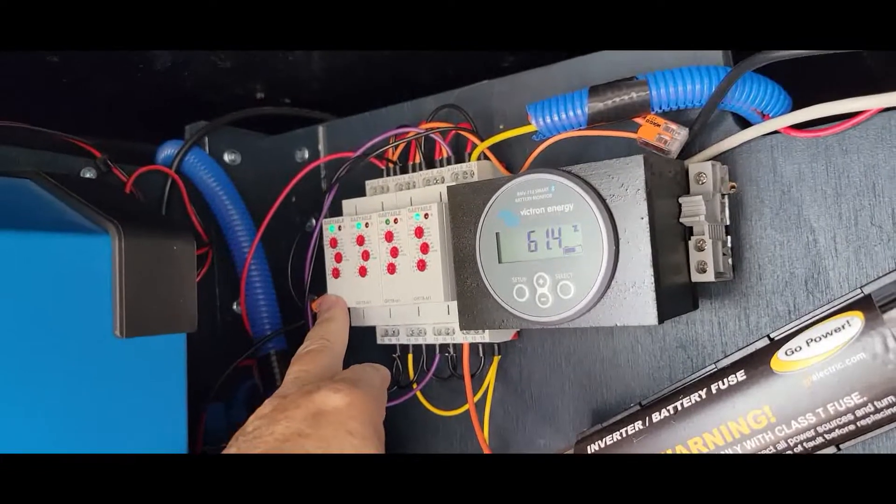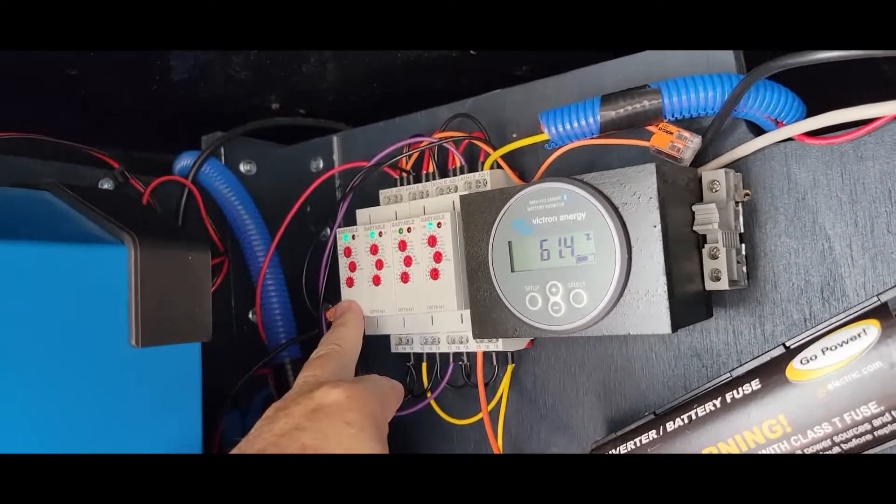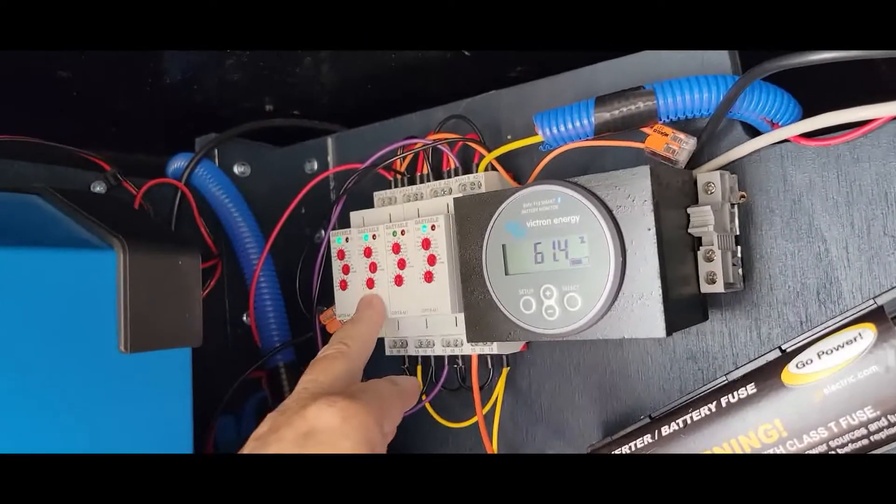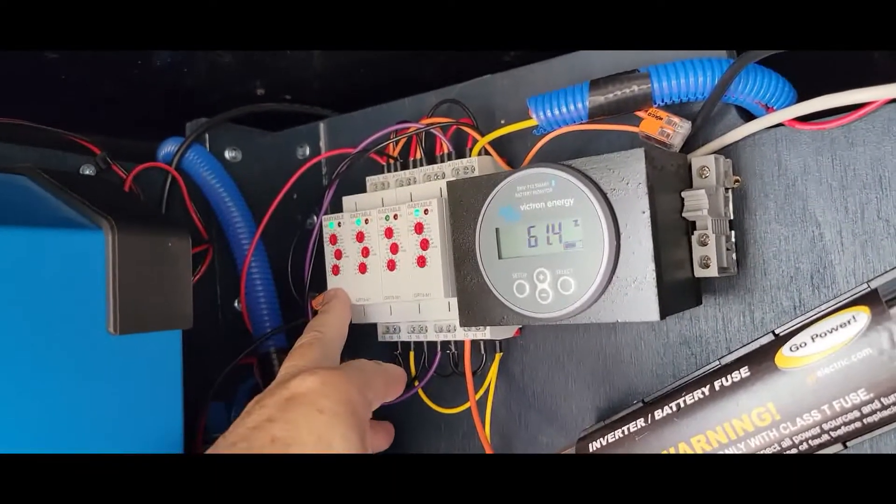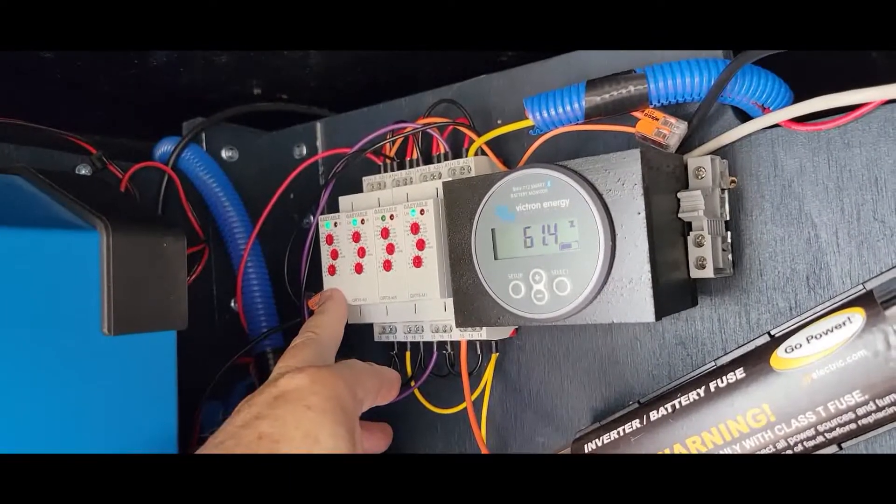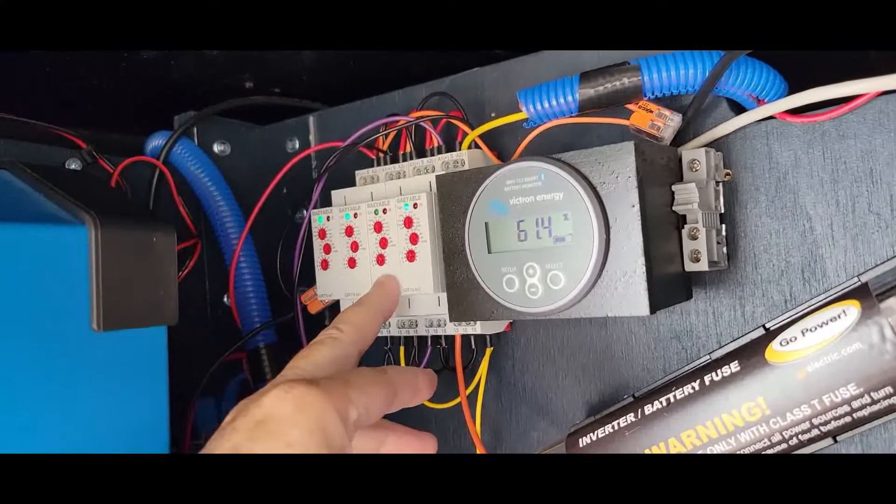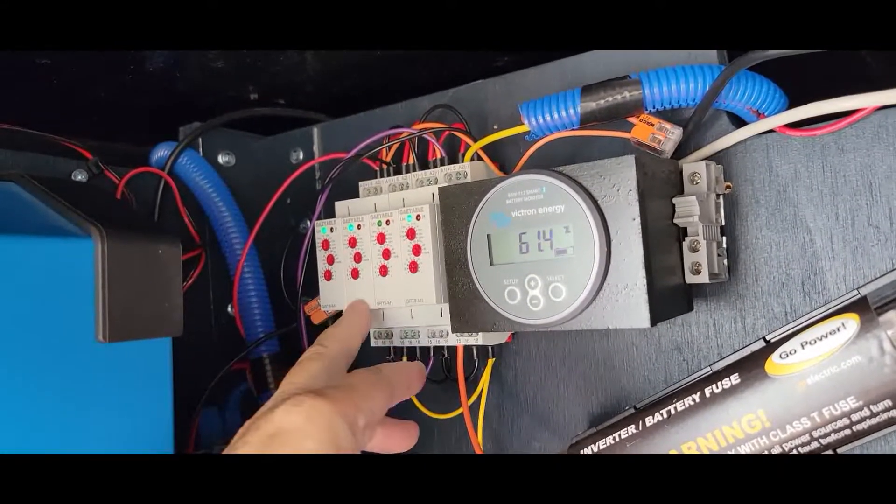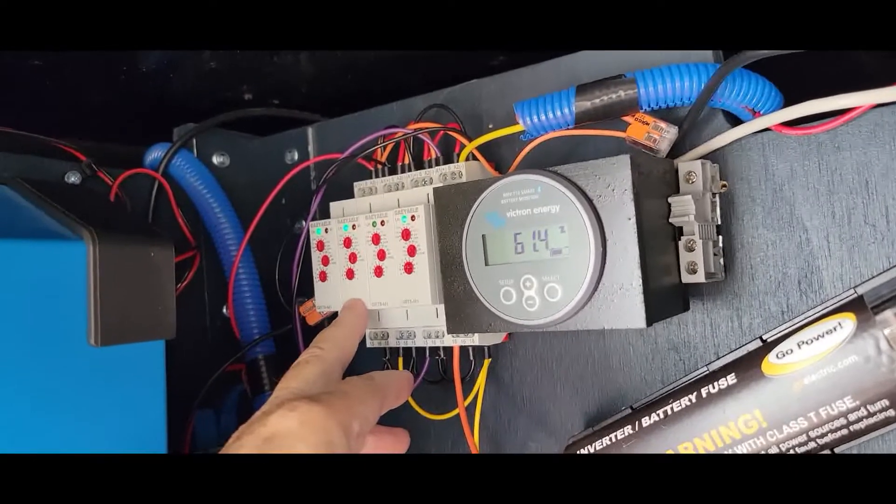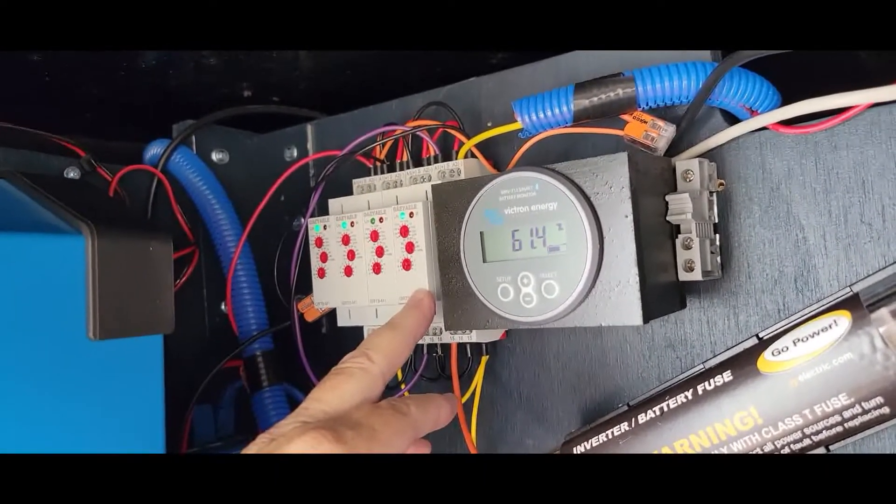The first relay is a stop that's also used as a prime cycle. The second one is a timer. This timer is set longer than the first relay so that gives a delay before starting which is the third relay. The third relay will come on when the second one has completed the time. The fourth one is my stop relay.